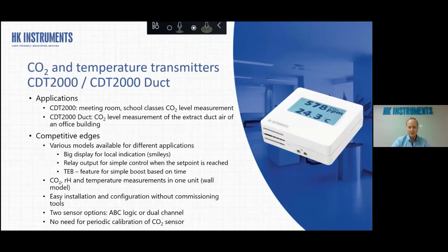We have this device, for example, for that purpose. So this is the CDT 2000. It's a CO2 and temperature and humidity transmitter for rooms. So the applications can be meeting rooms, and nowadays especially school classes for CO2 level measurement. So basically you can use this CO2 measurement in these kinds of rooms that are not always occupied, because then you can use this demand controlled ventilation strategy to save energy and make sure that there is always a decent amount of fresh air inside.